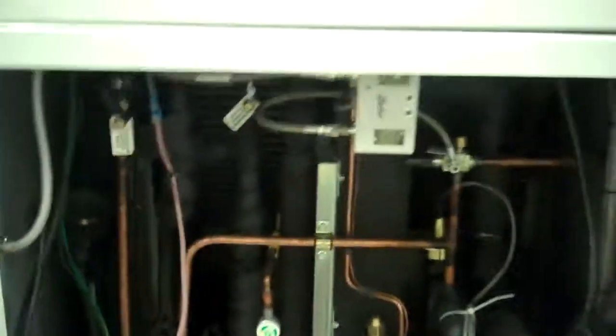So while I was talking, you heard the fan and the compressor just kick on. And we're starting to chill. It's important that you keep the side covers on all the time. This side cover and this side cover. And behind them they each have insulation running diagonally to meet up with the angle of the coils. It's important to have that seal, or else it'll go off on high pressure alarm. So I'll come back from video number 2 in a couple minutes. As you can see, we're starting to chill right now.